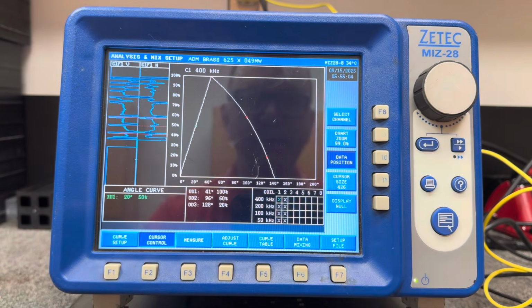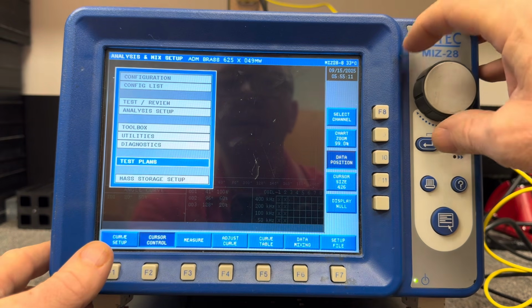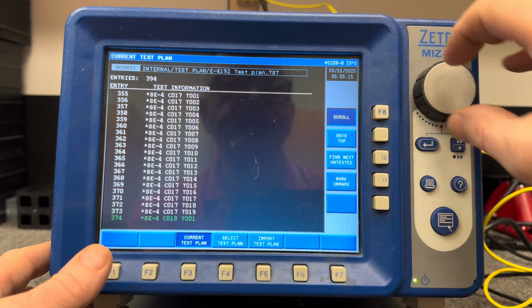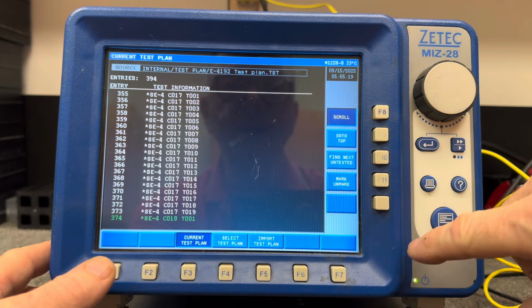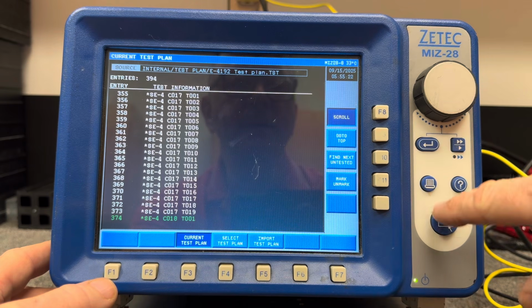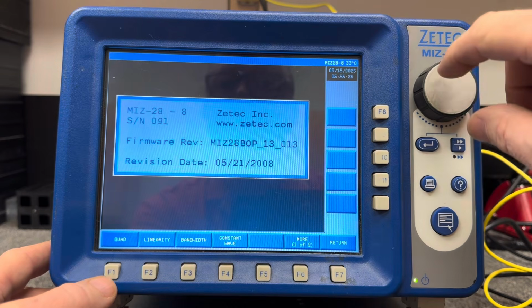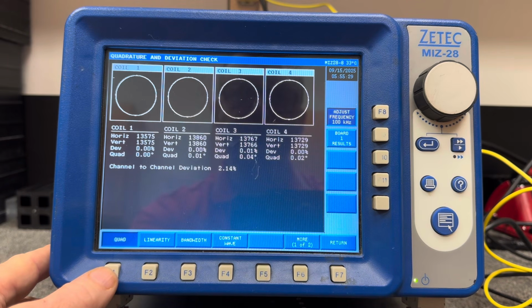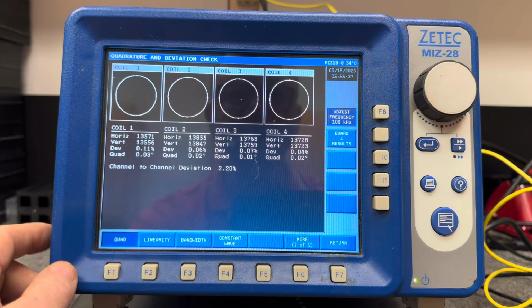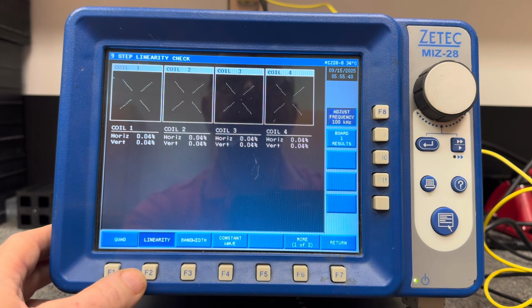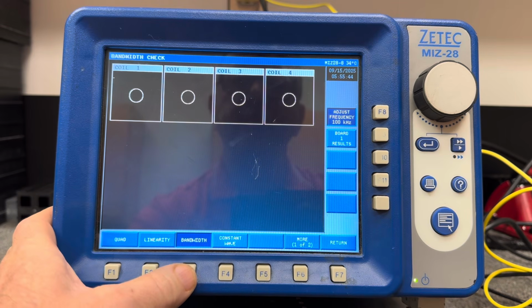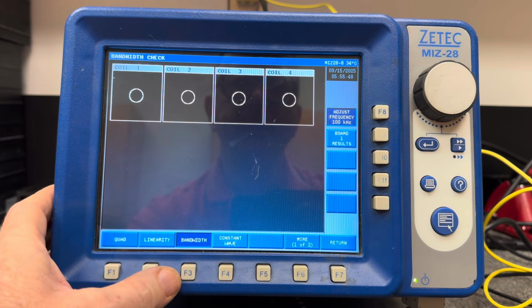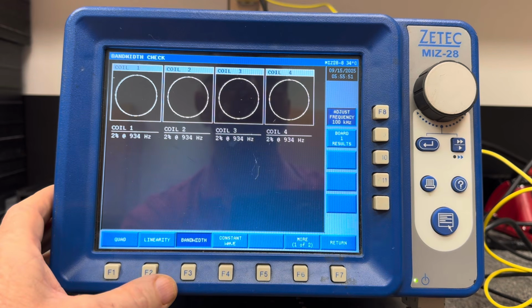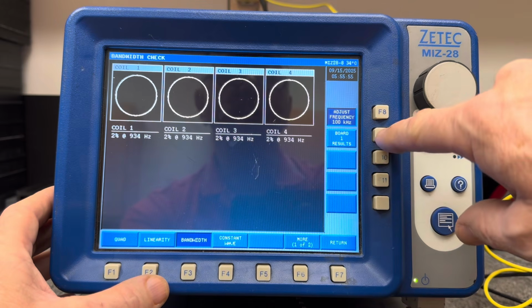you can go in here and make your curves and set volts and do mixes, all that sort of stuff. You can also go in here and you can load test plans for kind of streamlined acquisition. You can import your test plan. Let's see what else we got here. You got your diagnostics, so you can go in and you can check, you know, a lot of the functionality. This is calibration type stuff. So you can look at the channel deviation. It's less than 5%, which is good. Checks your linearity, bandwidth, and then of course if you send it out for calibration, they're going to hook up a test block and they're going to test even more stuff. But everything seems to be functioning just fine.